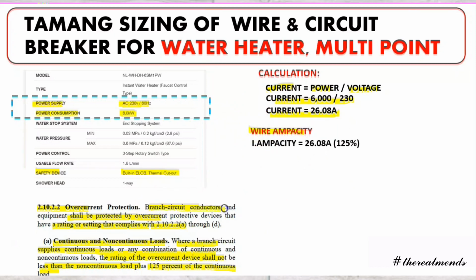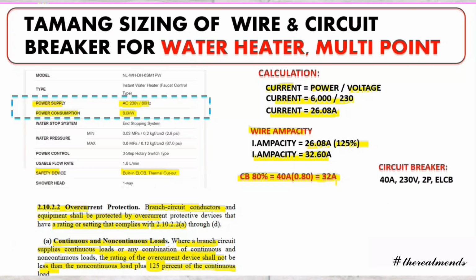This gives our wire ampacity, the branch circuit conductors and the equipment. Our current of 26.08, let's multiply that by 125%. We get a capacity of 32.60 amperes. If you use a circuit breaker of 40 amperes, it should only be loaded to 80%. If you multiply 40 amperes by 80%, we have a value of 32 amperes, which is closest to 32.6 amperes. Therefore, let's use a circuit breaker rating of 40 amperes, 230 volts, double pole earth leakage circuit breaker.